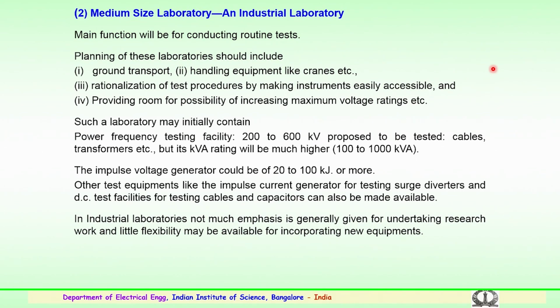or the rationalization of the test procedures by making instruments easily accessible, and also providing room for the possibility of increasing maximum voltage ratings and so on. So, such a laboratory may initially contain a power frequency testing facility, that is an AC facility, anywhere between 200 to 600 kilovolts. It could be proposed to be used for testing cables or transformers etc., but its kVA rating will be much higher, could be anywhere between 100 to 1000 kVA.